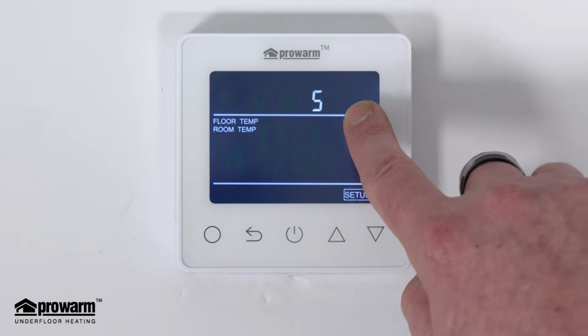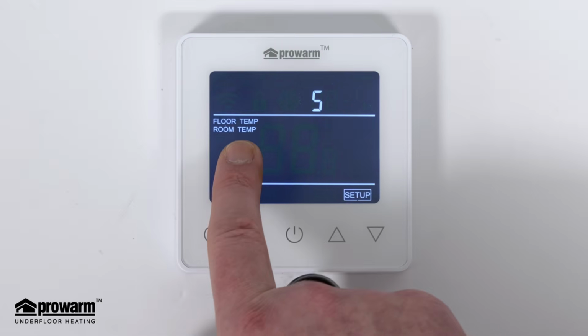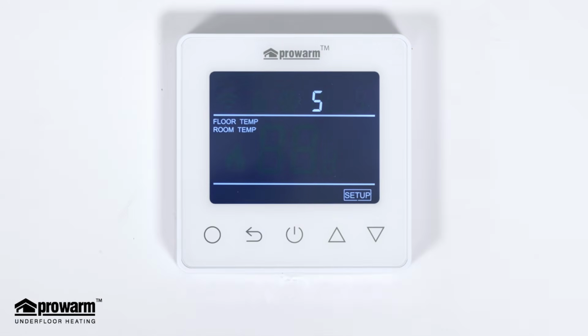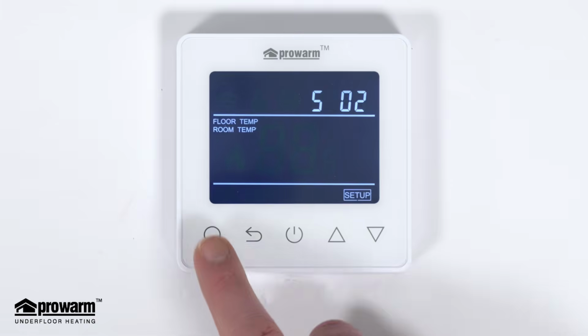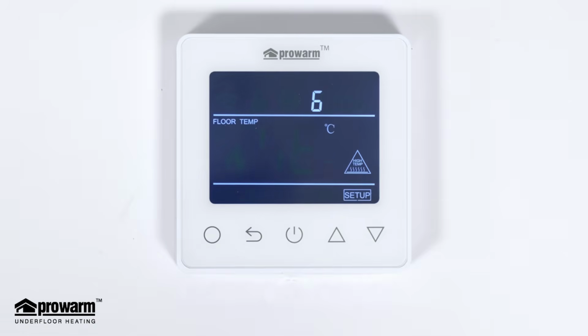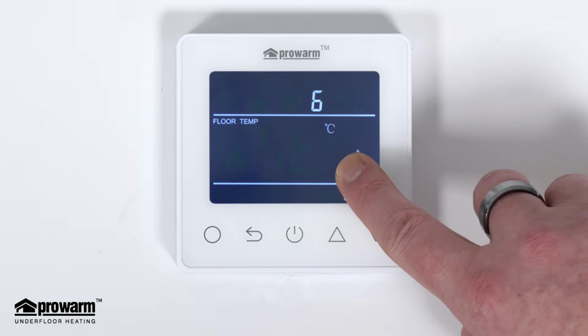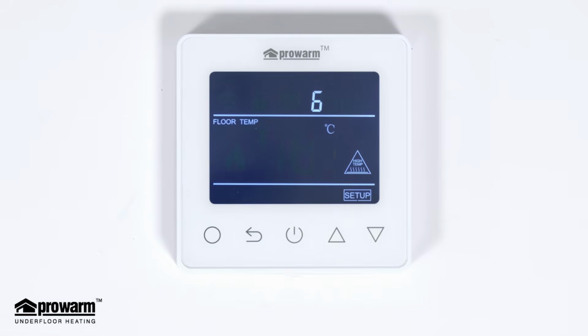When selecting both sensors, the room temperature will determine whether the thermostat calls for heat or not, but the thermostat will enforce the floor temperature limit, which is set in the next setting. This is currently set to 27 degrees. This is generally the optimal temperature to set your floor temperature limit to protect sensitive floor coverings such as wood, vinyl, and carpet.